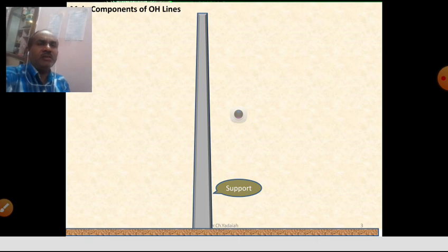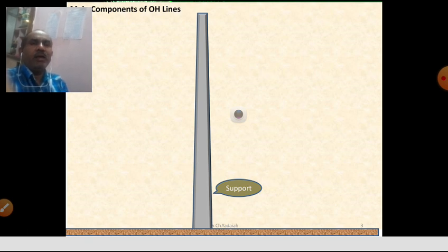In distribution lines, if you observe the 11 kV line, it uses 9.1 meter height PSCC poles, whereas sometimes we can use 8 meter poles. You can observe the cement poles in the street. The 11 kV line is somewhat higher compared to the LT pole, so you can easily recognize it by seeing the pole structure itself.